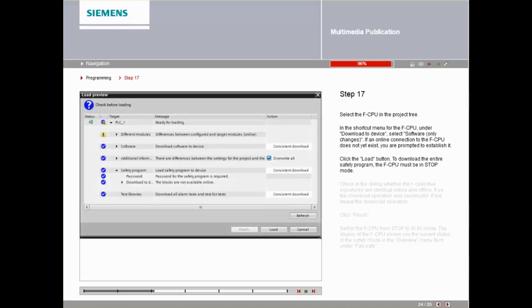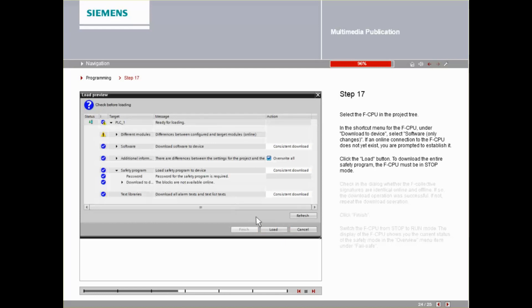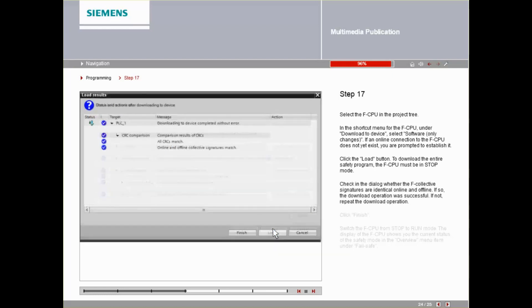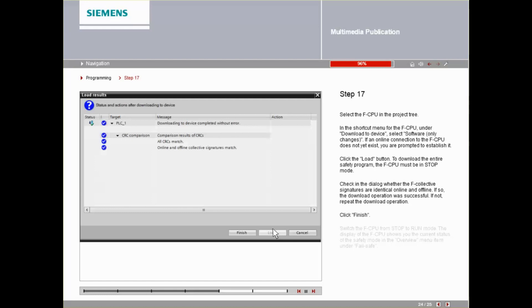Click the Load button. To download the entire safety program, the FCPU must be in Stop mode. Check in the dialog whether the FCollective signatures are identical online and offline. If so, the download operation was successful. If not, repeat the load operation. Click the Finish button.